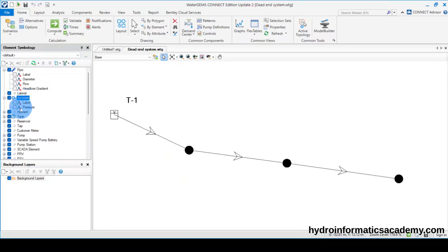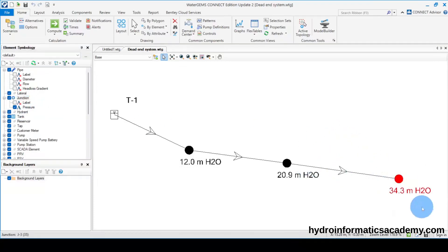For junctions, if I activate the pressure, you can tell that at this end point — the water tap where people will come and fetch water — the value we are having here is 34.3 meters of water column. What we always aim for is to make sure that pressure at this end point is maintained within six meters of water column all the way to 25, depending on which design manual you're using. But as you can tell, 34.3 meters is well above the required maximum pressure.